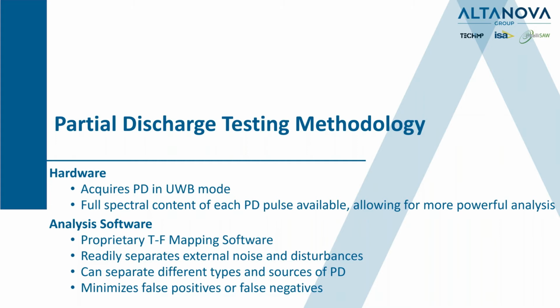I think the most important thing on this slide is the software that we utilize. Again, I mentioned it earlier. It's a proprietary TF mapping software. What that means is TF is time frequency mapping software. And why is that important? Well, as I was talking about earlier, we're measuring for RF signals. And unfortunately, there's a lot of RF signals, which we call background noise, that we don't want to look at. And when partial discharge was in its infancy, we had a lot of false positives and false negatives because we had a lot of background noise. And Techimp developed this proprietary software to actually separate the noise from the PD sources. All right, so it identifies the noise and then separates it, and that minimizes false positives and false negatives. And our software is patented.